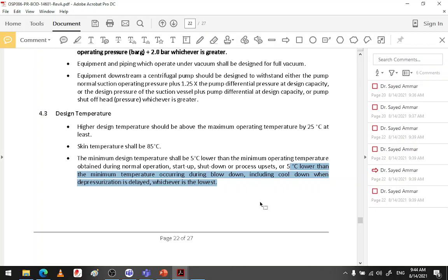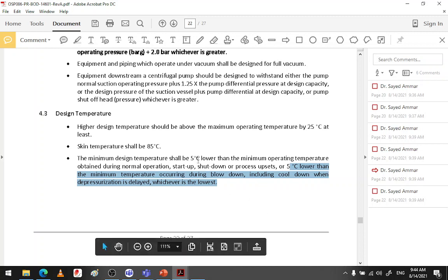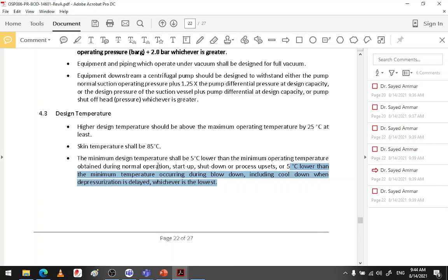I don't get it. Do you get it, Raja? What he is trying to say is that I would consider the minimum design temperature to be 5 degrees lower than the minimum operating temperature obtained during normal operation. If your separator is working at 50 Celsius, I would consider the minimum ambient temperature. The minimum ambient temperature in this area will be 10 Celsius. I will take 5 degrees lower than the minimum ambient temperature. Okay, if the minimum ambient temperature is 10 minus 5, your minimum design temperature will be 5C.